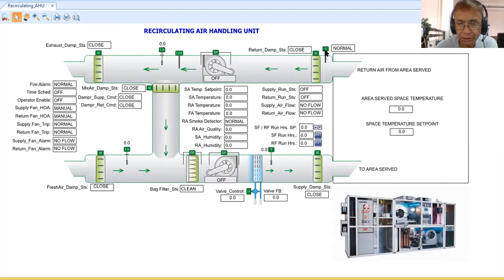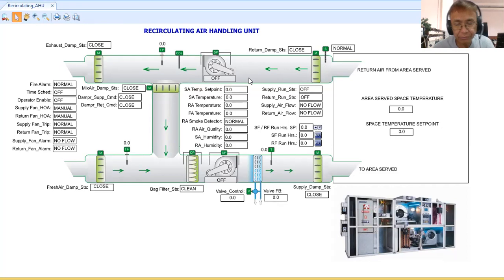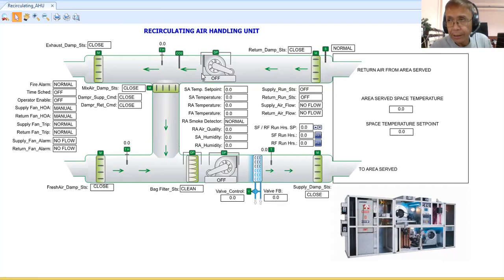At the return duct, there are several devices. First, a smoke duct detector senses the air for any smoke coming from the area being served. If smoke is detected, the air handling unit should stop — that logic will be included in the program. There is also a CO2 detector to monitor air quality. If the air quality becomes poor or the air is dirty, a procedure must be implemented.